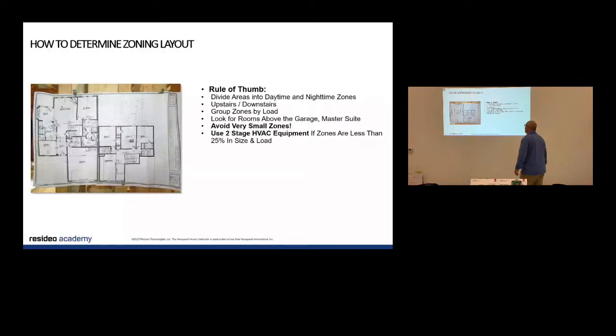When you are laying out zoning, let's not make really small zones in a house. If we make small zones in the home, we're gonna have noise, we're gonna have some bad equipment, things can happen, so be smart about it. I know you guys probably aren't laying out a lot of the zoning, but just for principle, if I got 2 floors, that really should be 2 zones. Maybe the master bedroom would be a 3rd zone, but master bedroom generally doesn't need a whole lot of CFM, so you're gonna have to be pretty smart about how you do the ductwork into there.